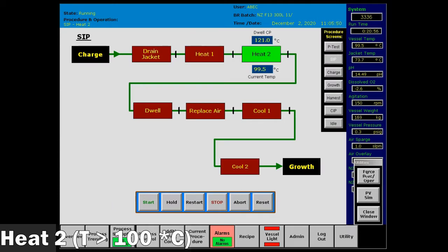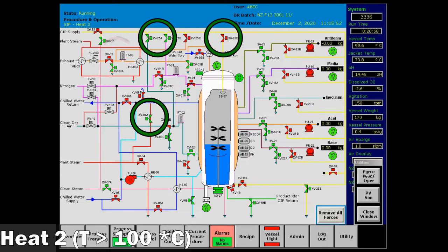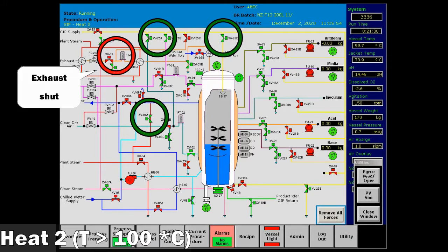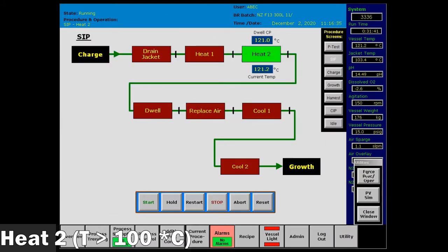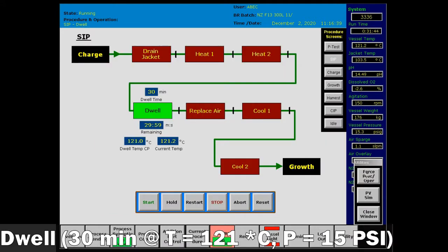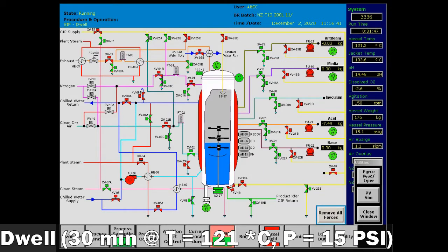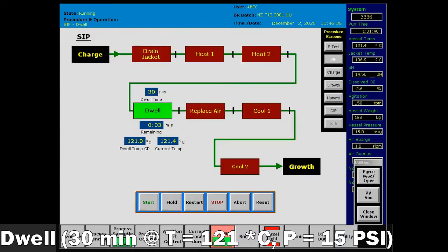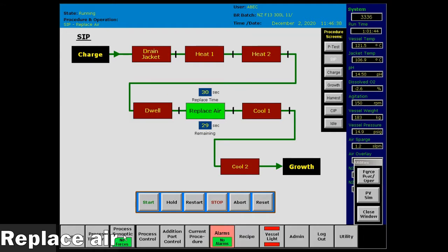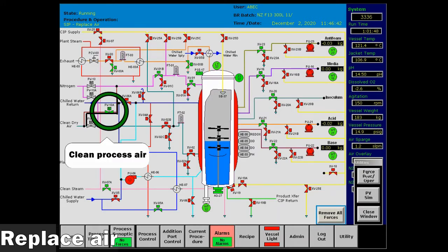Once the Heat 1 temperature set point is reached, the exhaust valve closes. Pressure gradually increases to facilitate temperatures greater than 100 degrees C. Heating continues until the vessel temperature is equal to the SIP set point of 121 degrees Celsius. The vessel temperature is at 121 degrees Celsius. The reactor enters dwell mode, a 30-minute holding period during which the temperature is maintained constant. Once the sterilization time is up, the air inside the reactor is replaced by directing clean process air through the overlay filter, and any heating is discontinued.